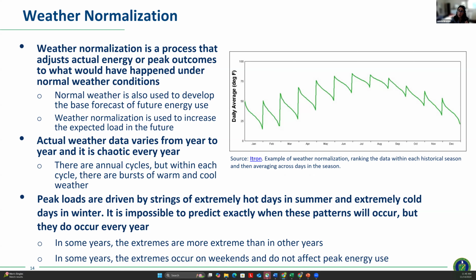Distribution utilities that perform weather normalization want to understand what the normal load is, so they don't miss cases like the peak happening on a weekend with lower load, or whether it was an extreme event, and try to normalize that for planning. What they typically use when applying statistical normalization in distribution planning is the 90th percentile load or weather, meaning a 1-in-10 extreme weather event is used to calculate that peak load.